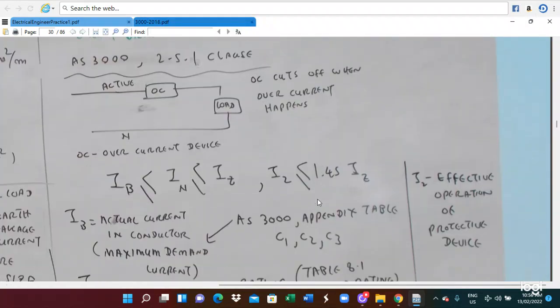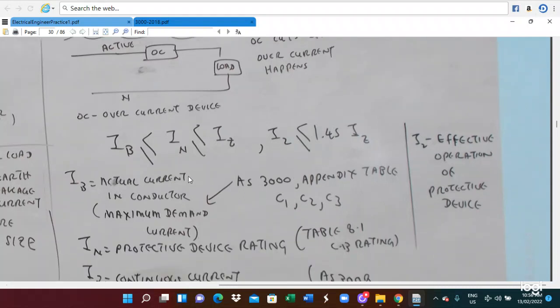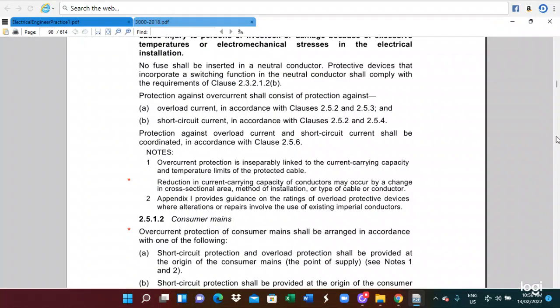Therefore, the important aspect is that there are three aspects: the actual current of the consumer conductor, which is the maximum demand current, IB. IB means the actual current in the consumer conductor, the maximum demand current. Maximum demand current means that when you install the electrical installation, you install the light point, the socket outlet, any lighting point, and also heater. We have to refer to AS 3000 Appendix C1, C2, and C3, so that we look at the appendix C1, C2, C3 of AS 3000.